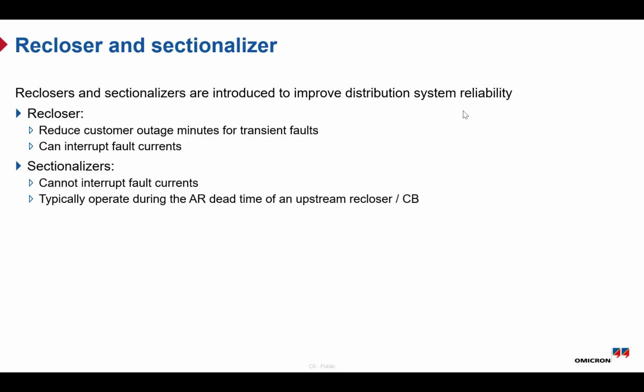Now let's look at the sectionalizer. A sectionalizer cannot interrupt the fault current by itself. Instead, it works together with the upstream recloser. It counts the number of fault interruptions and then opens during the dead time, meaning when the upstream device is open and there is no current flowing. So in simple terms, the recloser clears the fault and the sectionalizer helps to isolate the faulty section. Together, they improve system reliability and reduce the number of customers affected by outages.